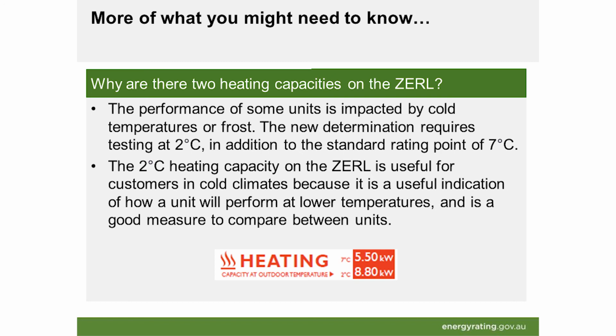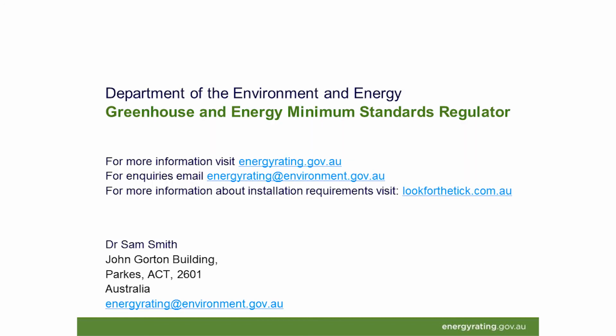Some units will have a lower heating capacity at 2 than 7, some it'll be about the same, some will be more. Generally, if you're in a cold climate, look for units that are at least as good, if not better, at 2 degrees than at 7. What this isn't giving you is an indication of how efficient the unit is running at 2 degrees, but it'll tell you how much heating it can provide.